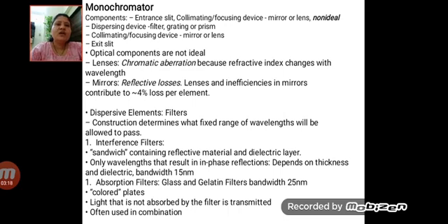There are two types of filters: one is called the absorption filter and the other is called the interference filter. They are wavelength selectors. A narrow bandwidth enhances the sensitivity of both emission and absorption methods, and is frequently a requirement from the standard point of view, for obtaining a linear relationship between the optical signal and the concentration. Absorption filters are used for the visible region, and interference filters are used for UV, visible and IR. They are called Fabry-Perot filters.